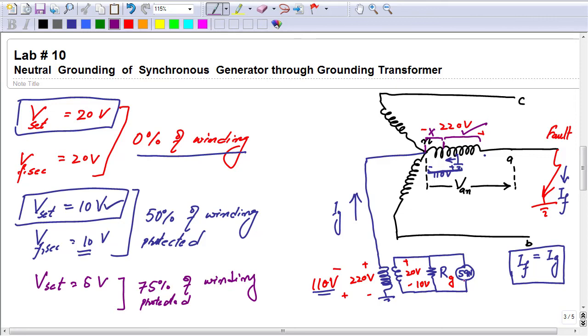Now we want to set the Vset of the relay in such a way that it is protecting 90% of the winding. Vset should be selected so that if a fault occurs from the neutral point up to 10% of the winding, only this portion is unprotected, and if a fault occurs from 10% up to 100%, this is the protected portion. We want the setting of this relay such that it protects 90% of the turns of this generator. I will leave this calculation, what the value of pickup should be so that it provides protection from 10% to 100% of the turns, which makes 90% of the winding. So the student will do this calculation to find the value of Vset.